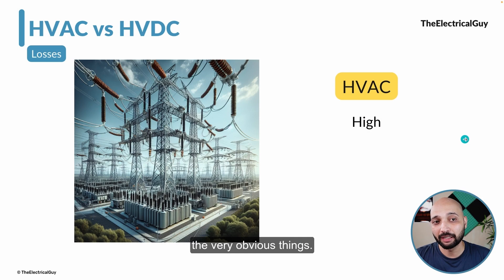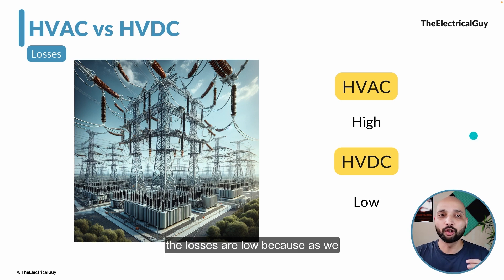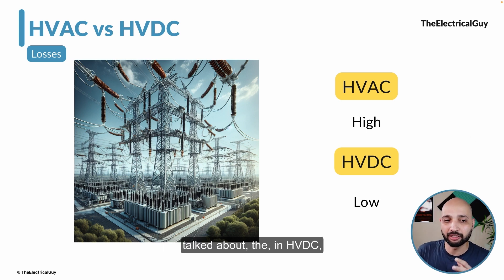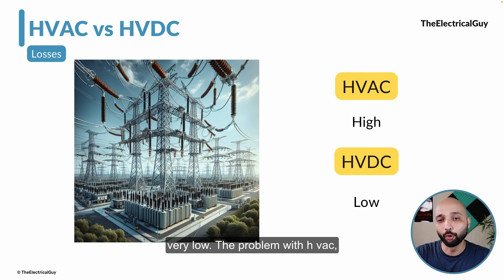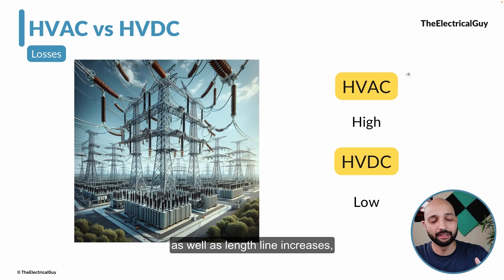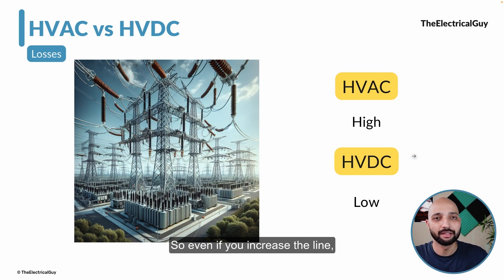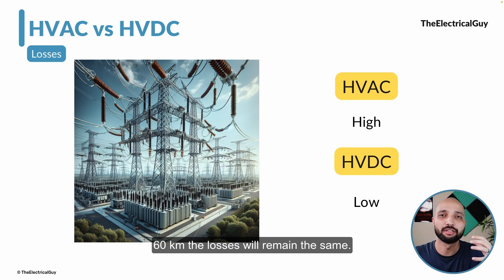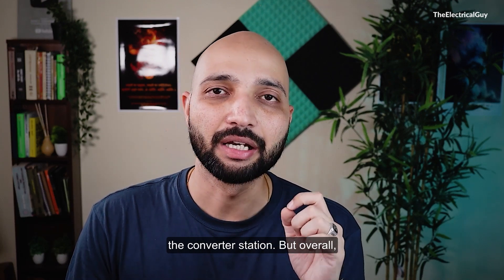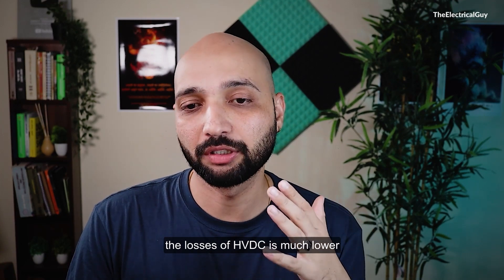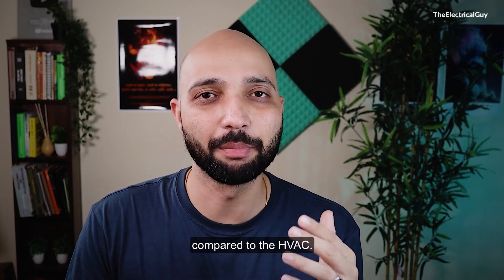Moving on to the very obvious parameter: losses. In HVAC, transmission losses are very high. In HVDC, losses are low because only resistance plays a role — there is no inductance or capacitance. The problem with HVAC is that as line length increases, losses also increase. But with HVDC, losses remain relatively constant even as line length grows. There are some losses in the converter stations, but overall the losses of HVDC are much lower compared to HVAC.